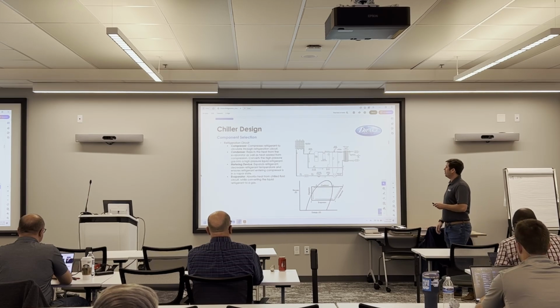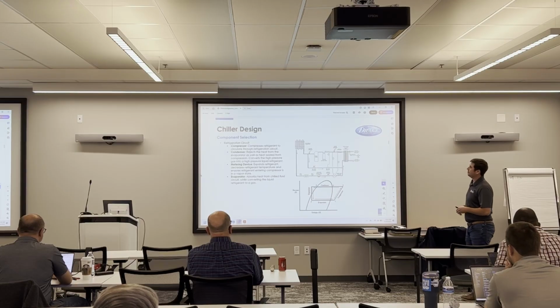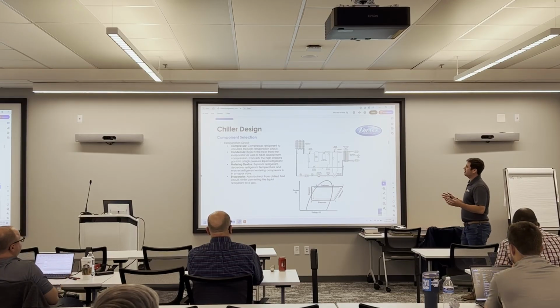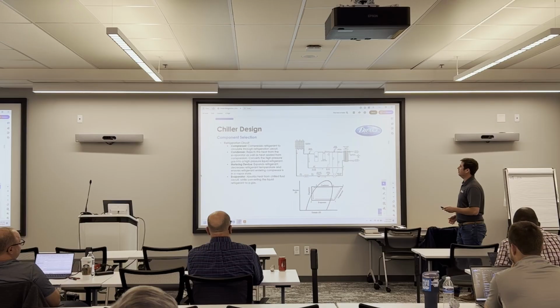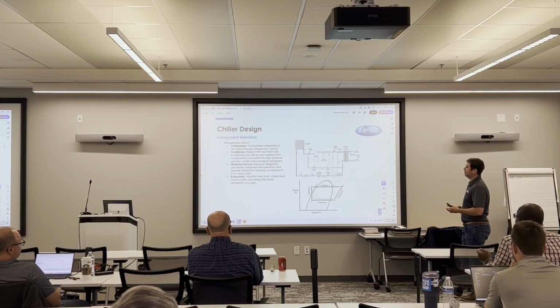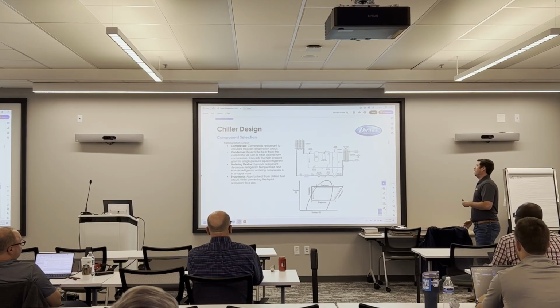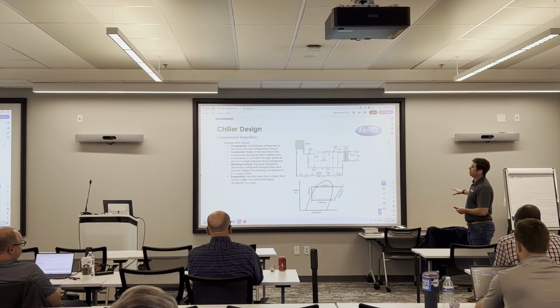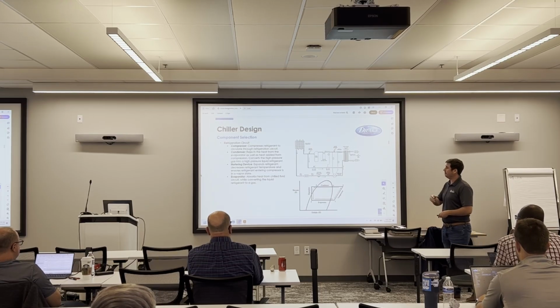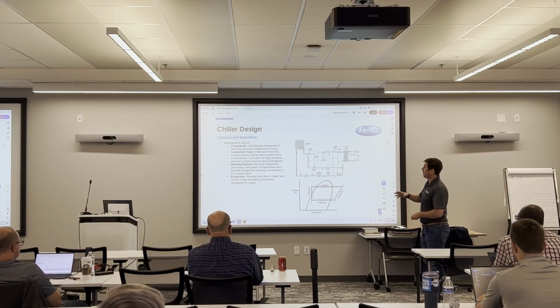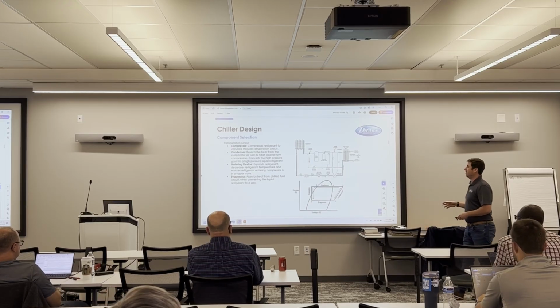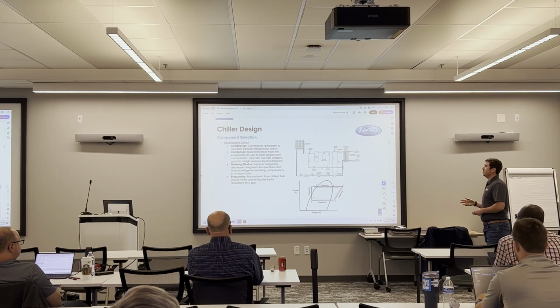Out of our evaporator, it's going to travel into our compressor as a low pressure vaporized gas. The compressor is going to take that refrigerant and essentially circulate it through the rest of the circuit. It's kind of like your driving force, think of a pump. So it's going to put additional heat onto the refrigerant, but also take it from that low pressure vaporized state to a high pressure vaporized state. Then it circulates the refrigerant through the condenser. The condenser is going to reject the heat that we absorbed from the evaporator as well as the heat added from the compressor. It's going to convert it from a high pressure gas into a high pressure liquid.